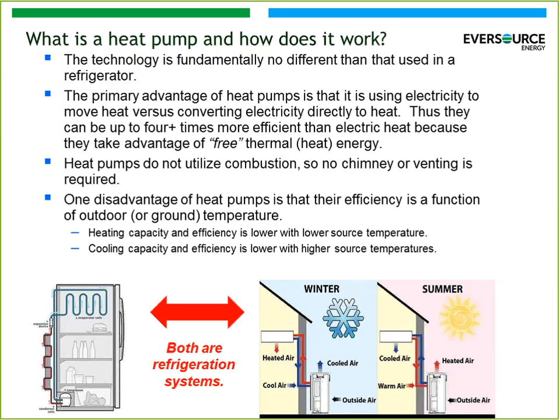Likewise, when they reverse themselves and provide cooling, they're going to be most efficient and provide the most capacity on a 75 or 80 degree day. When it's 90 or 95 degrees, their capacity is going to be a little bit lower and their efficiency is going to be a little bit lower. And I think we know that intuitively from the cooling side, but it also applies to the heating side as well. And as we move through this presentation, you're going to see examples of how this works and what are some of the design challenges, and ultimately what are the effects of having a heat pump technology where the capacity and the efficiency varies versus a traditional fossil fuel type of system where the efficiency and the capacity remains pretty much constant, relative to the outdoor temperature.